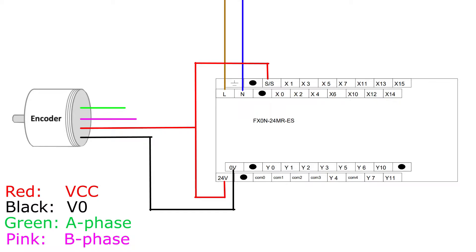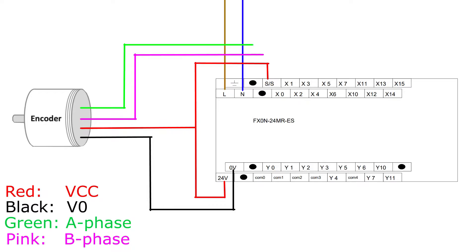And the A and B phase we can connect to any of the digital input terminals on the PLC. I will connect them to digital input 0 and 1. This is basically how we wire up an encoder to a PLC.